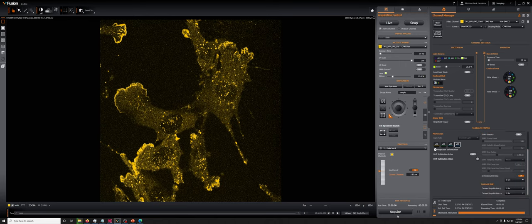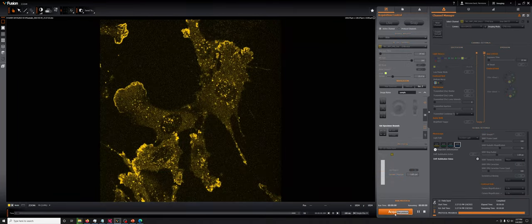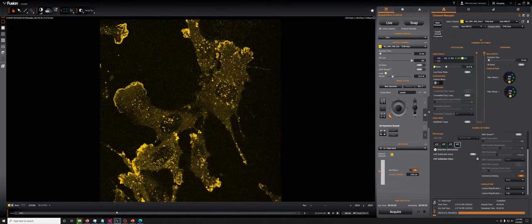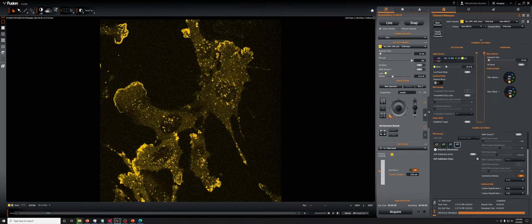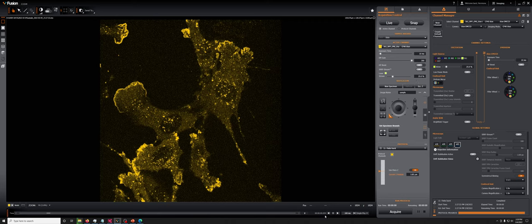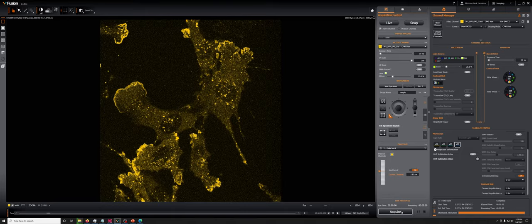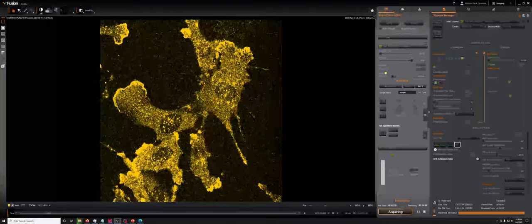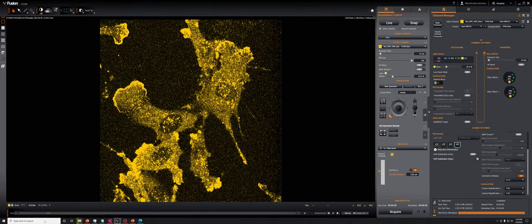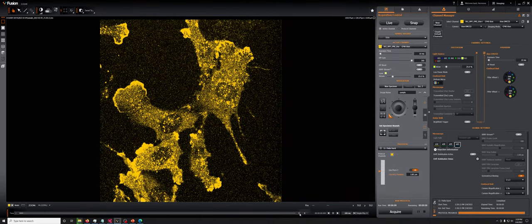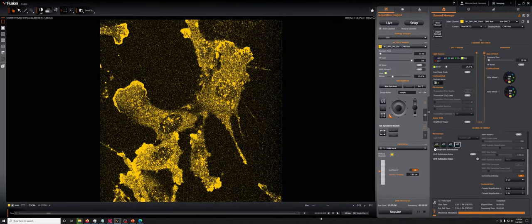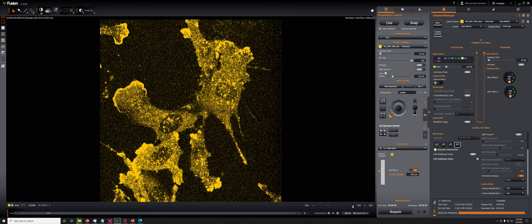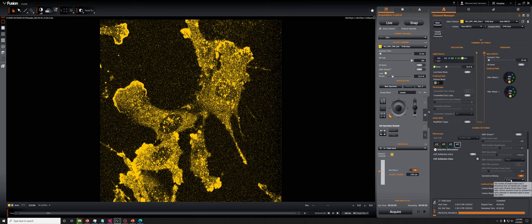you can see that between the first and the second, I expected 10 milliseconds, but I got 39 milliseconds between them, which means I have an extra 29 milliseconds, which came from reading out the camera. If I switch the binning from 1 by 1 to 2 by 2, and I acquire this again, the expectation is that that number will go down. And so let's see, between the first and the second frame, it took 20 milliseconds. So instead of 10, it took more. It took 10 milliseconds more, but before it had taken significantly more than that. So we dropped that extra time between frames by doing the binning.